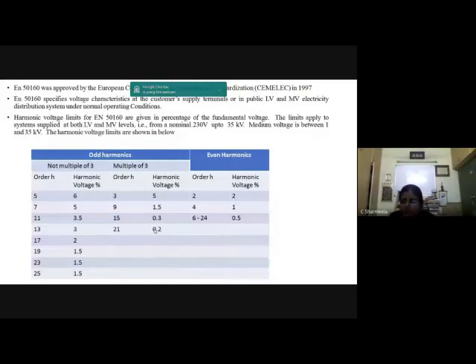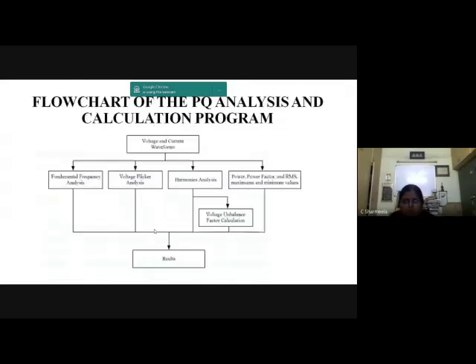And according to it, it should not violate the norms prescribed for the individual harmonics, odd and even harmonics, which are given in the table. So this is another simple calculation program developed by a few researchers for estimating the power quality problem. They capture the voltage and current waveforms and pass them on to the algorithm. This algorithm will try to determine what power quality problems are present by taking the fundamental frequency for analysis.